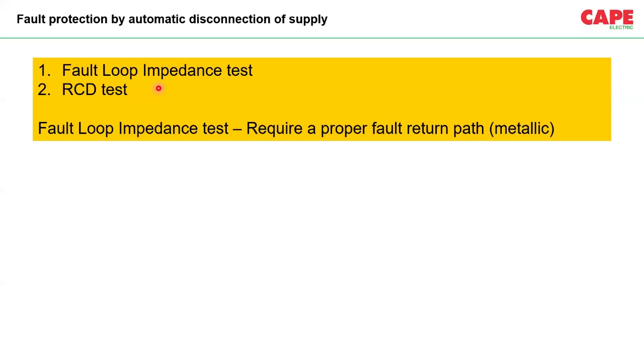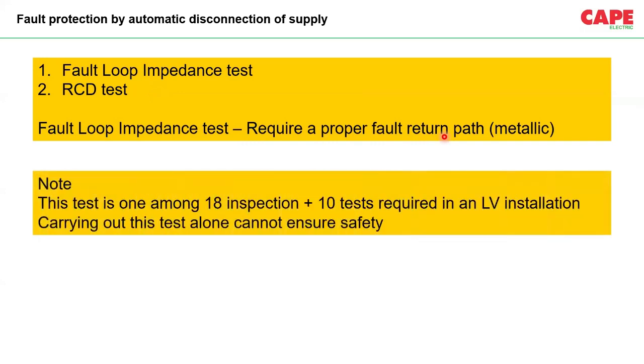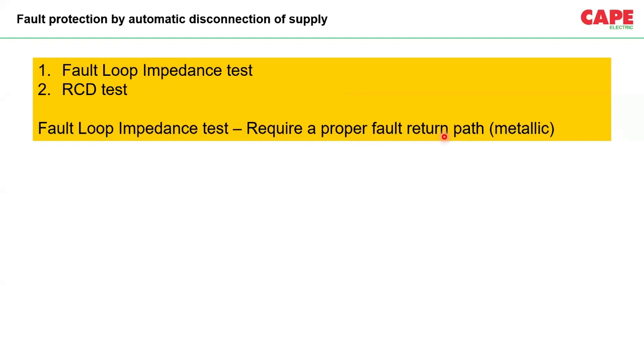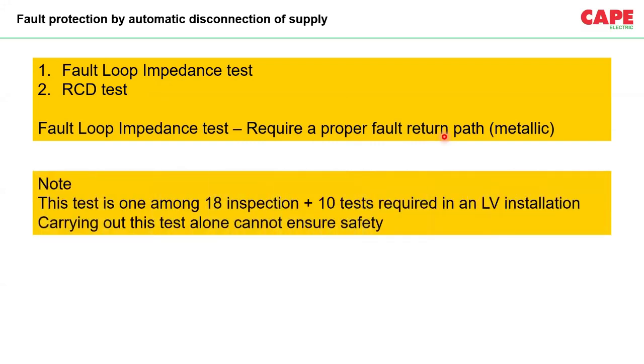And you should also understand that for the fault loop impedance test, you require a proper metallic fault return path. So if the metallic fault return path is not there, then the first test will not work out. You have to always use a 30 milliampere RCD, and with the 30 milliampere RCD, you cannot operate your industry, or run your hospital, because it will sometimes create noise and tripping.